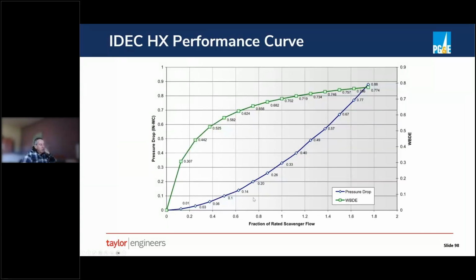Similarly, for the flow rate through the scavenger fan, which is sort of the outside air side of the heat exchanger, pressure drop is going to go down with the flow, how much you speed up and slow down that scavenger fan. And by slowing down the scavenger fan, you still get a lot of good heat transfer, wet bulb depression effectiveness, even at very low speed on the scavenger fan. So the efficiency stays pretty good or arguably gets even more efficient because you get such a low pressure drop, such low fan energy, and you're still getting a lot of effect. So it's a system that has very good part load performance.